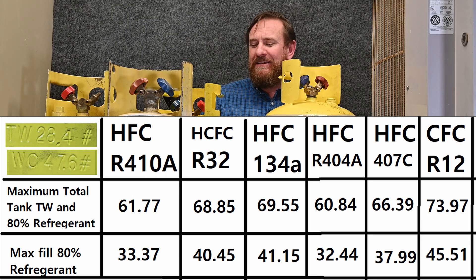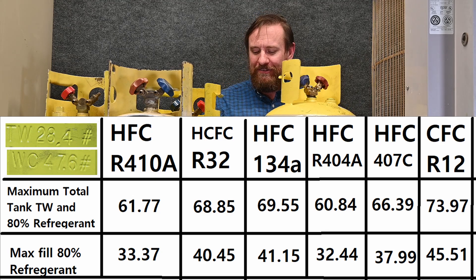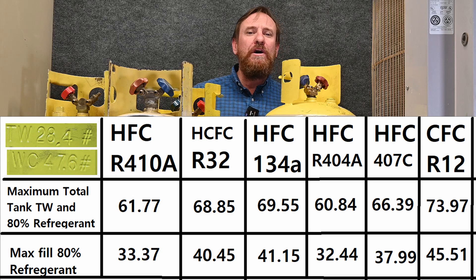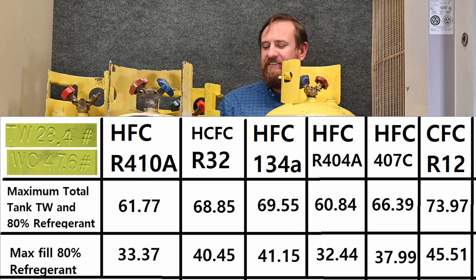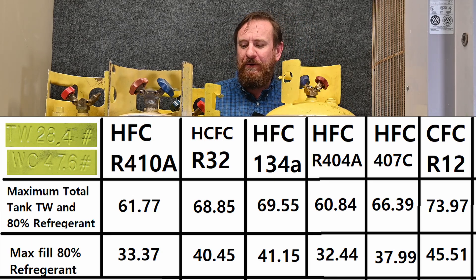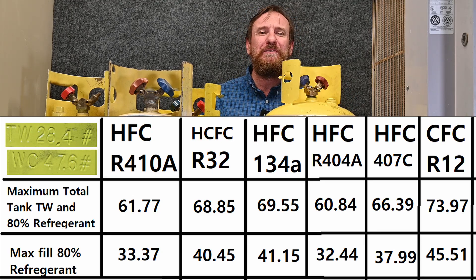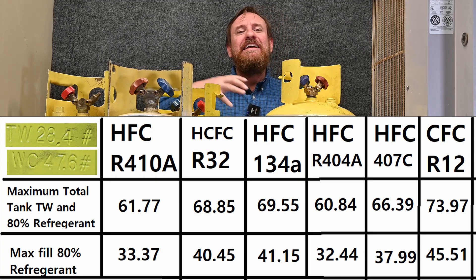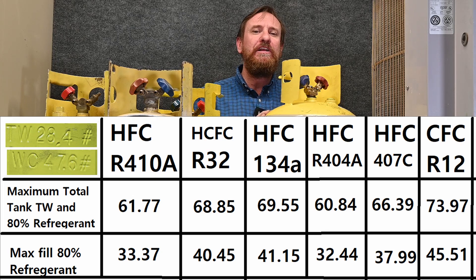Now let's switch over to R12 — this is cool. With R12, the tank and its contents would hold 73.97 pounds of refrigerant. That's a whole lot of weight difference. If it was R12 alone at 80% full, it would be 45.51 pounds of refrigerant. Our water capacity at 100% was 47.6, but R12 at 80% gives 45.51 pounds — almost as much as water at 100%. Hopefully that gives you an understanding that different refrigerants take up different volumes and have different weights. We don't have just one number we can use.